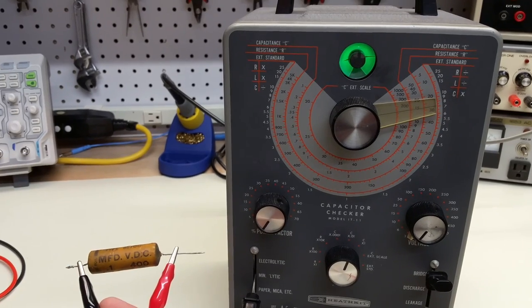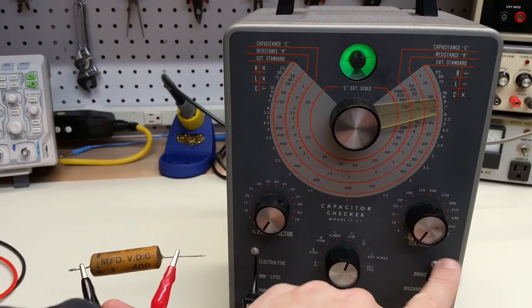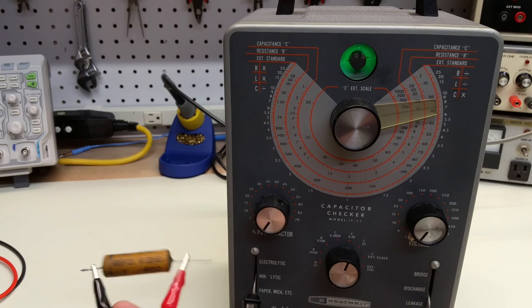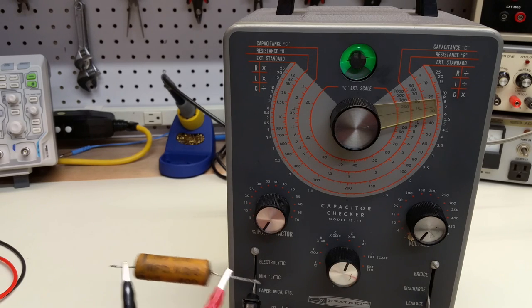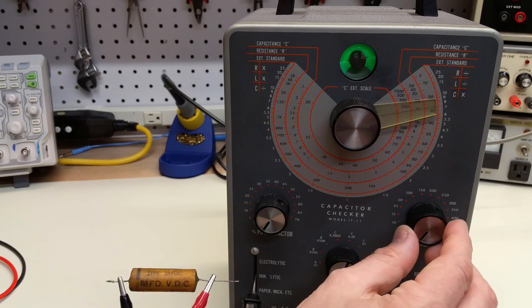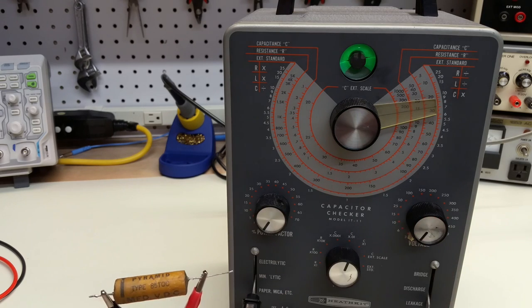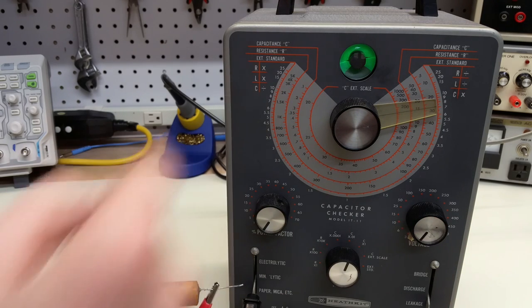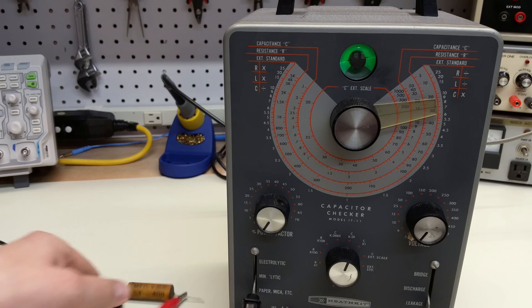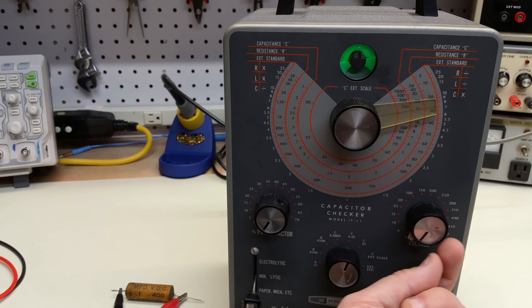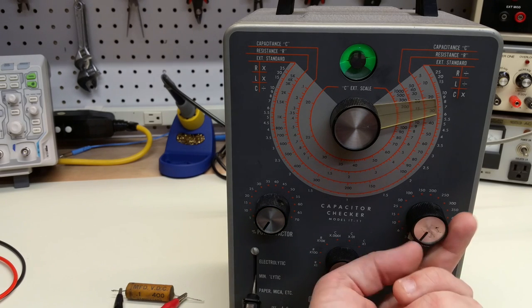So the way that you test that is you move this out of bridge and down to the leakage arm, all right? And then you change the voltage reading and see if the eye remains open. So we're going to do that here. This is now at 3 volts and it's not leaking.